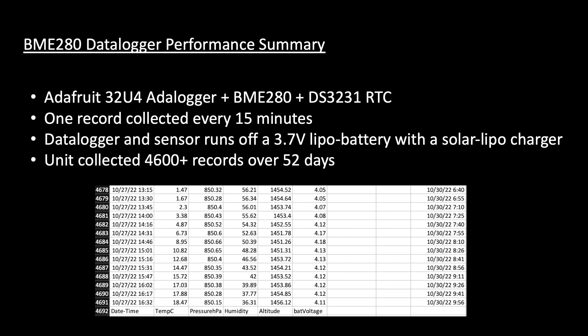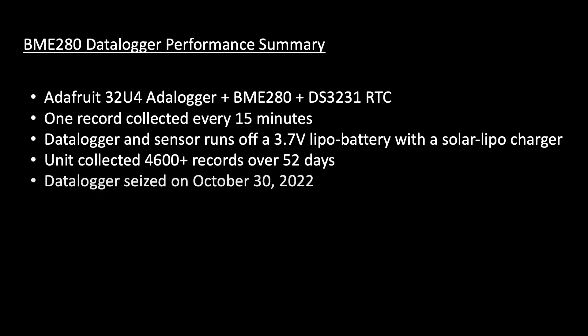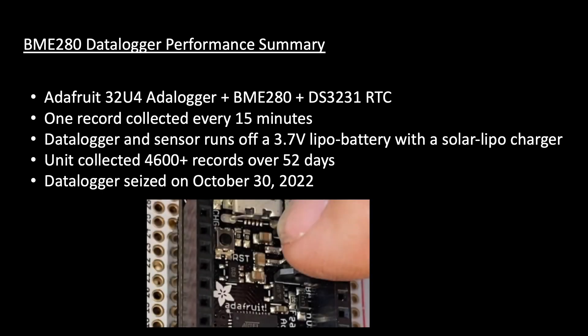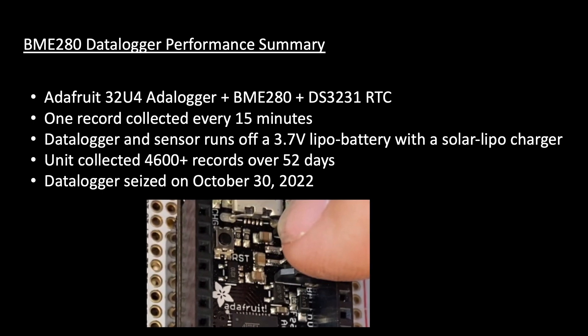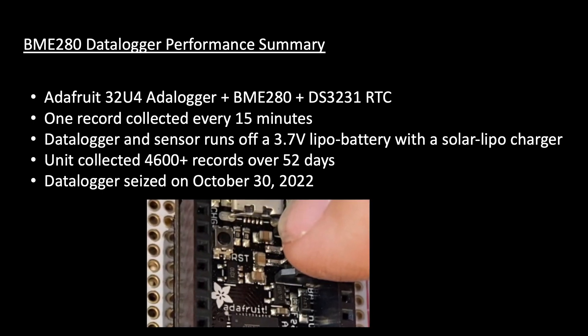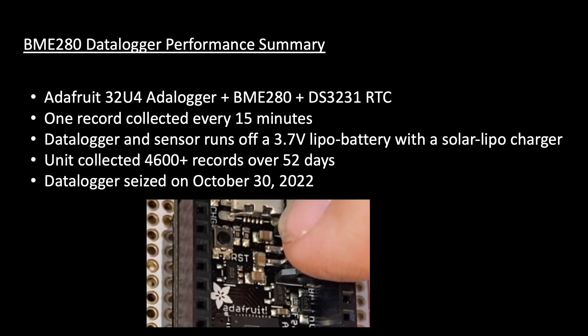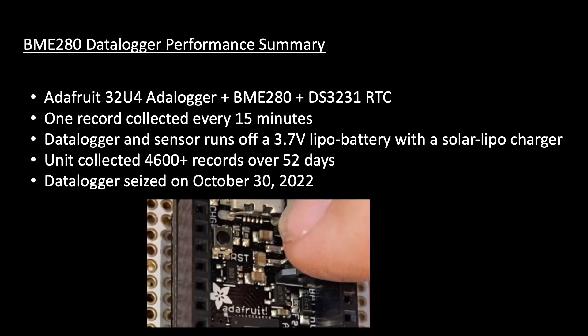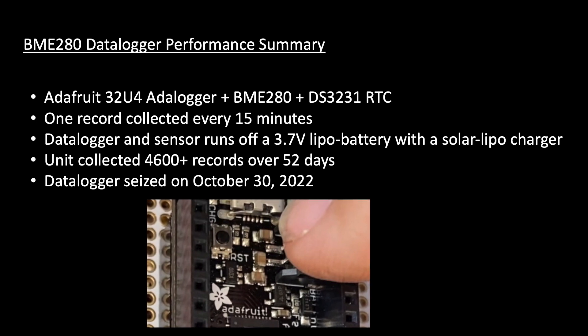The data logger ceased to function on October 30th. Upon resetting the board, the unit picked up where it left off without any issues. The reason for the system locking up in October is unclear to me at this time. A simple remedy is to reset the unit during routine field visits to clear out any memory or hardware issues that may be contributing to the system locking up.